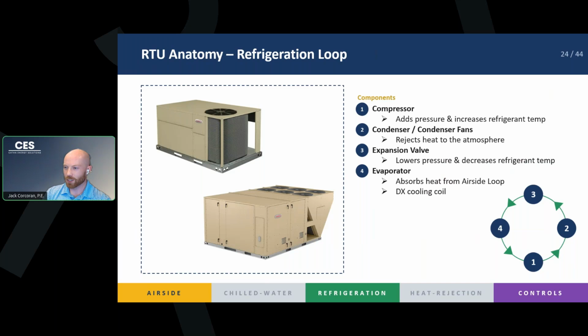They actually reject the heat to the atmosphere. So you can imagine bigger condenser coil, bigger condenser fans, or more condenser fans, bigger capacity. And the top one only has one fan and a smaller condenser coil, so that's a smaller capacity unit. Rooftops look all sorts of shapes and sizes, but these are just two of them. But they take advantage of the refrigeration loop, just like our VRF system.